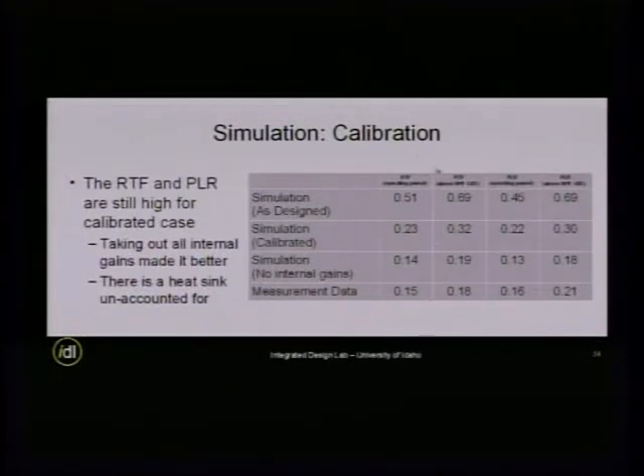And as you can see, immediately it has the cycling on and off. But still, it's not too good. If we compare the runtime fraction and the PLR, the measurement says 15%, 0.15, and calibrated, it's still 23%. And the PLR is also way too high, too different. So I did another case where I simply took out all the heat gains. No internal gains, so only climatic conditions. And guess what? With no internal gains, it's close, really.